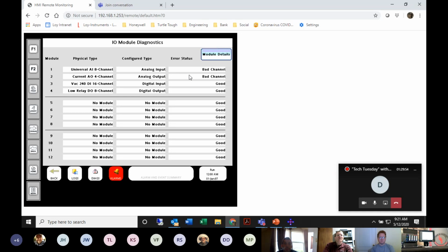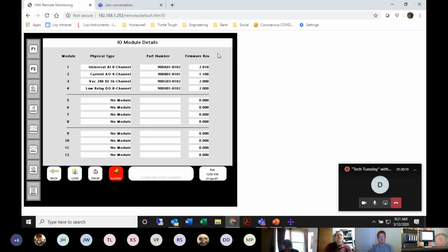And on my analog output, since I don't have a 4 to 20 hooked up to a motor or something else out in the field, it's indicating an open channel. So if I did think I had a bad card, I can go to module details, and it will tell me for that 1st slot the part number and the revision level for that particular card. So if you wanted, in your troubleshooting, to take one off the shelf or get one off our shelf, you would look for this part number, 900A01-0102. You would then give that to us or take it to your crib, find that card, and take it out.